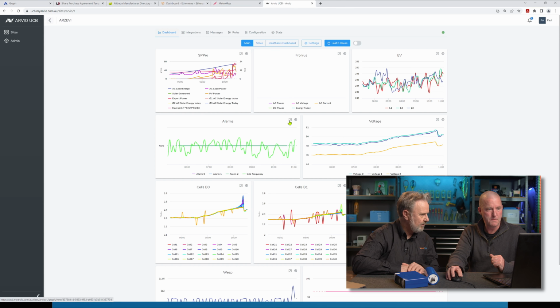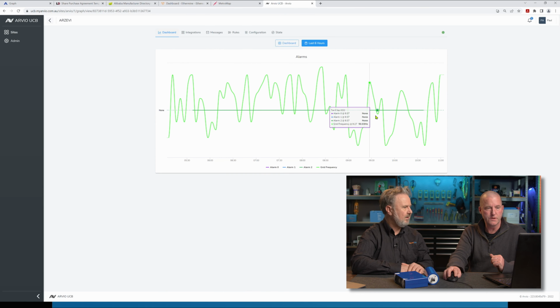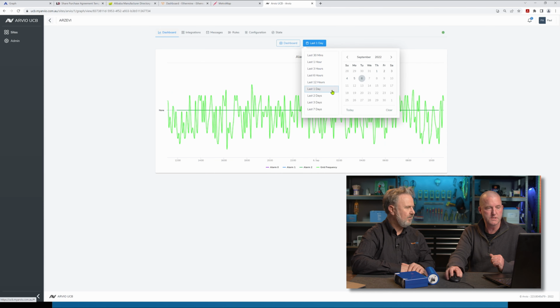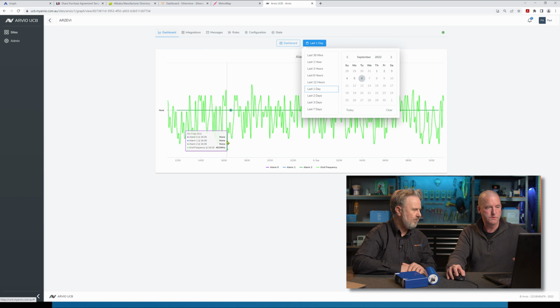So this is grid frequency you're monitoring? Yeah, this is grid frequency just through the SP Pro, to 2 decimal places. And this is the last 6 hours. You can go back a longer period if you want to, last day. You can see it jumping around everywhere. So what's the limit on those axes? How much frequency shift do we see? The lowest one's got 49.94 hertz there. So that was an FCAS event there.